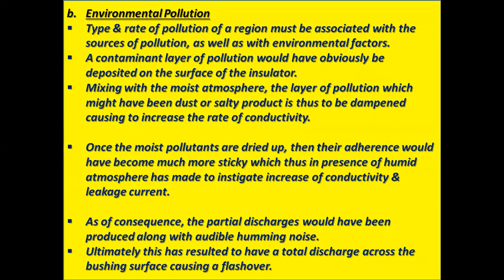Once the moist pollutants are dried up, their adherence becomes much more sticky, which in the presence of a humid atmosphere instigates an increase of conductivity and also leakage current. As a consequence, partial discharge would be produced along with an audible humming sound or humming noise. Ultimately, this results in a total discharge across the bushing surface, causing a flashover.